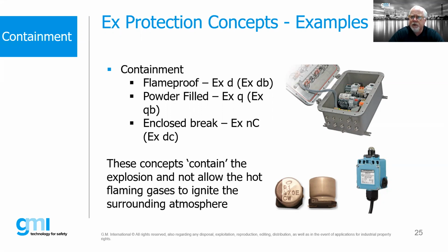A flange type enclosure like what you see in the upper right hand corner is an example of an EXD box with a flange type design. The important thing to remember on EXD is that we need to take especially good care of all of the flame paths. The flame paths are the flanges. They could be threaded joints, the thread entries, if you will, for any cable glands or stopping plugs. Those are all flame paths as well, so we need to take very good care of them. One of the downsides of flame-proof is that we really cannot modify these products once they come out of the factory. So we cannot add additional entries or additional components, generally speaking, once they're certified and once they leave the factory.